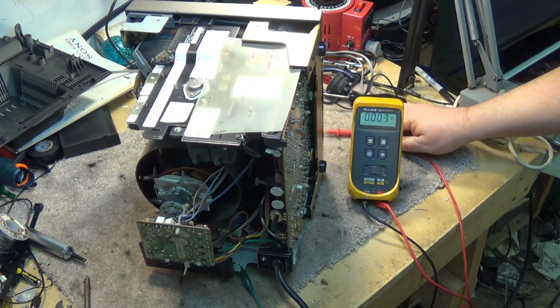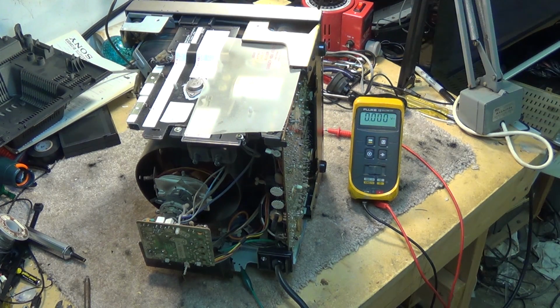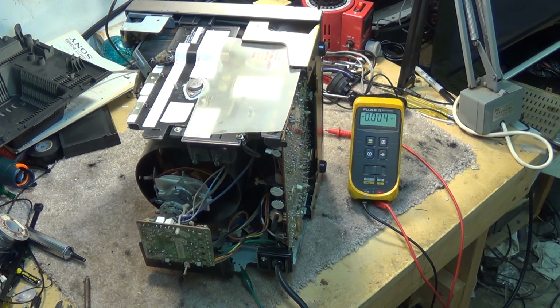The next thing we want to determine is whether our horizontal circuit is operating. For that I'm not going to use my meter, because if it's running there could be about a 1,000 volt pulse on it, which would blow the meter up.